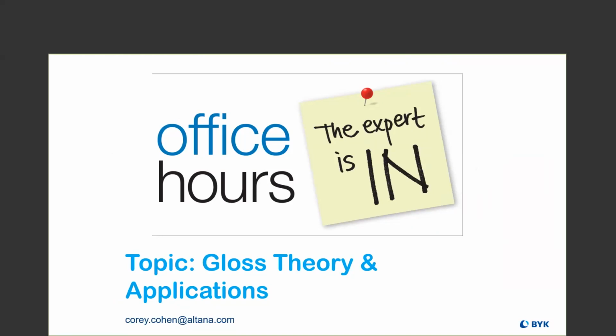Corey answered one that I often get. A lot of times people report gloss in percent, and it actually is gloss units. Percent is percent reflectivity. People think that if gloss goes from 0 to 100 and I have an 80, that's 80%, and it's not accurate. It's 80 gloss units. It's probably one of the most common I get.